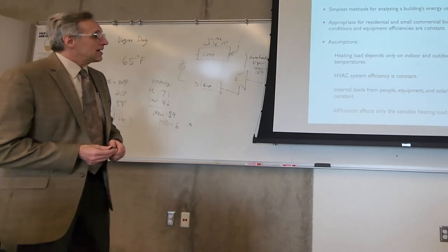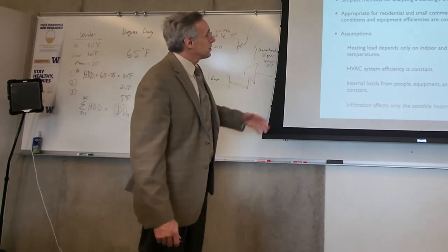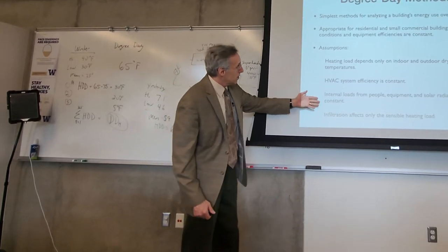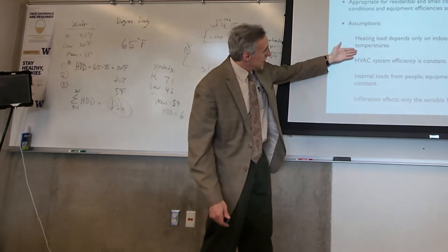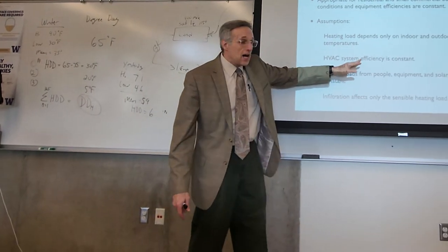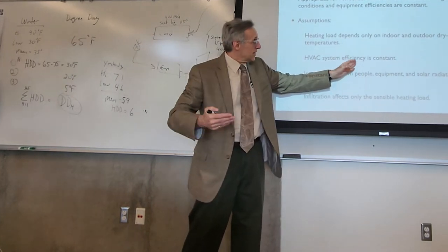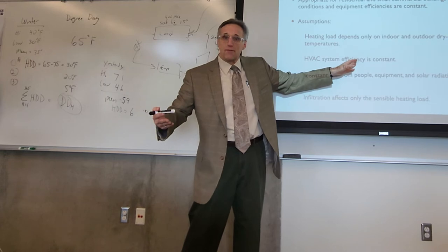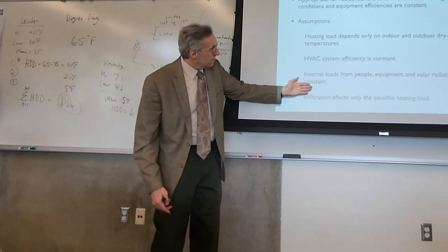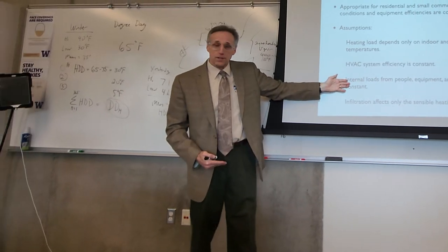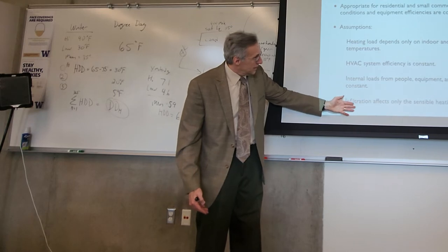Okay, so anyway, that's the concept here. There's a lot of assumptions built in here that are questionable. So this is a rough approximation. HVAC efficiency is usually not constant. It's more efficient when it's part loaded, and it gets less efficient as you load it really heavy. And typically you've got internal loads that are not being taken into account here: people and whatever's going on inside the building.